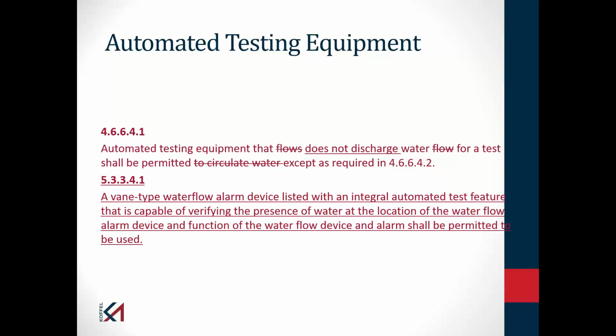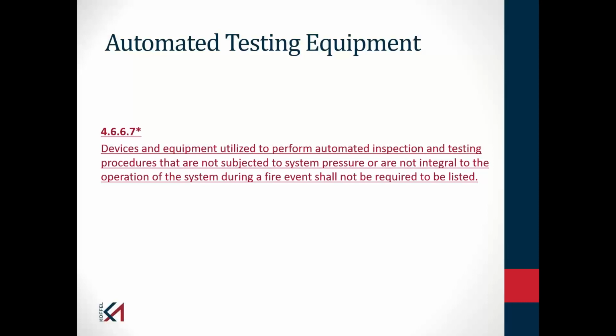One of the arguments we had in the past in the committee was, well, if you don't flow water, how do you know there's water in the pipe? Maybe we're just moving this switch and getting a signal that says we have water flow. We don't really know if there's water there to flow in the pipe. So one manufacturer has now developed a water flow switch where, when I put it in test mode, it moves the paddle so that we close the set of contacts and I get the alarm signal. And then when I terminate the test, it measures how long it takes for the paddle to reseat itself. That delay in reseating itself is what lets me know there's water in the pipe. If there's no water in the pipe, the paddle would go right back to its original non-alarm position.